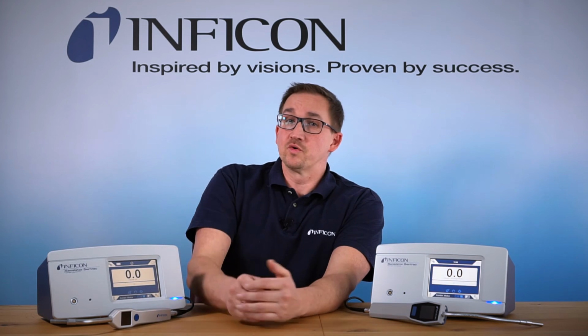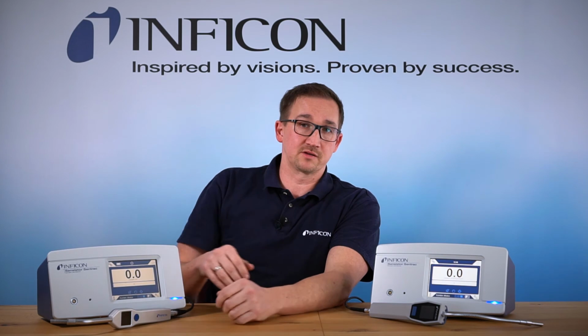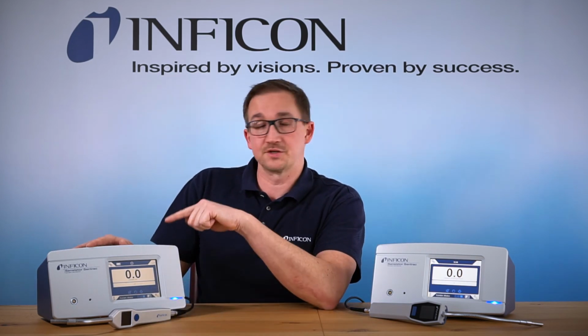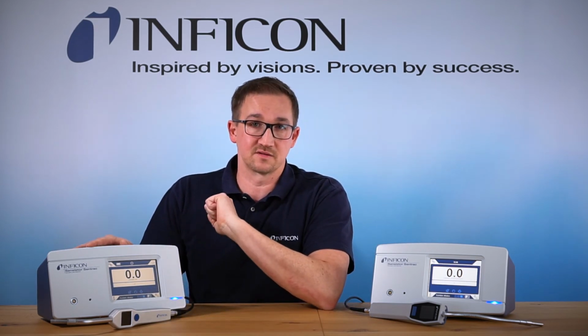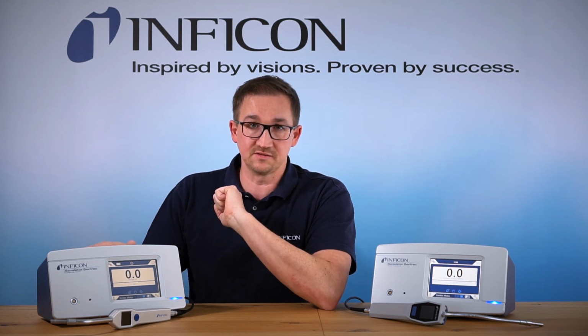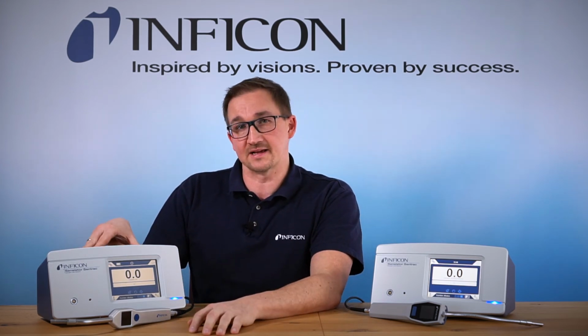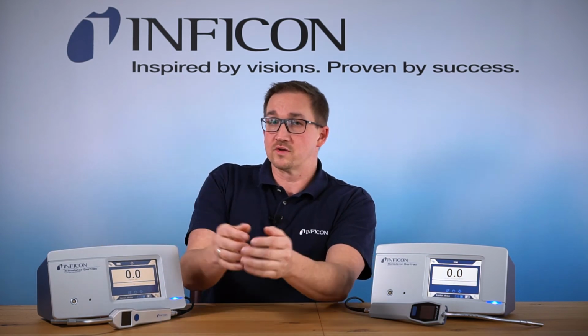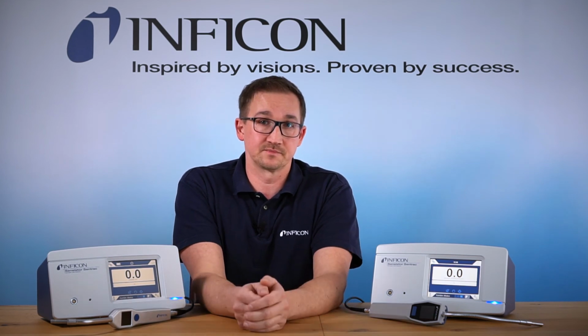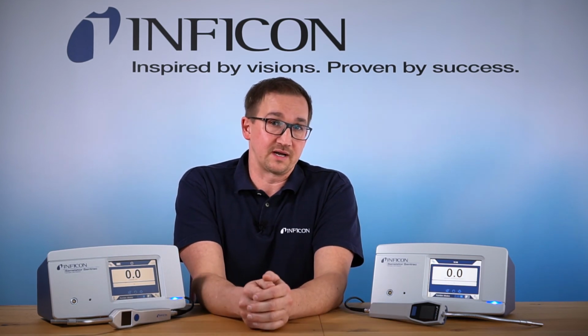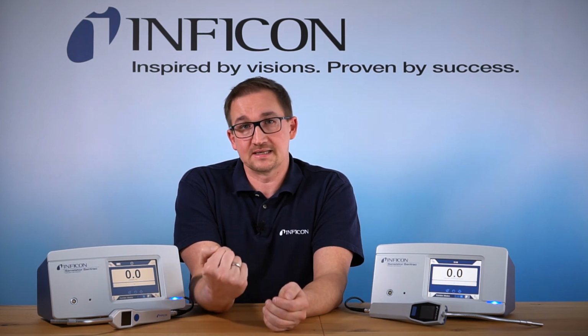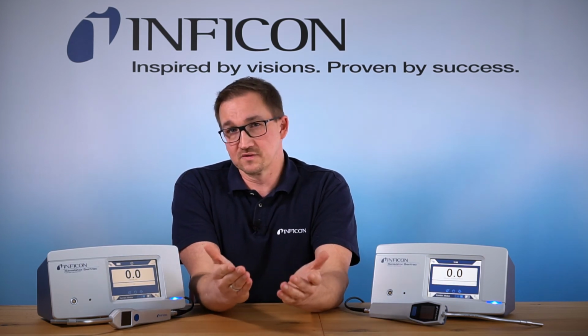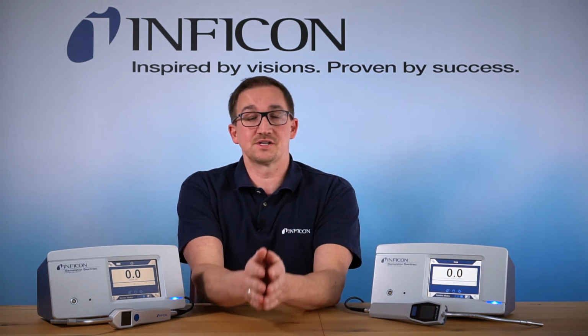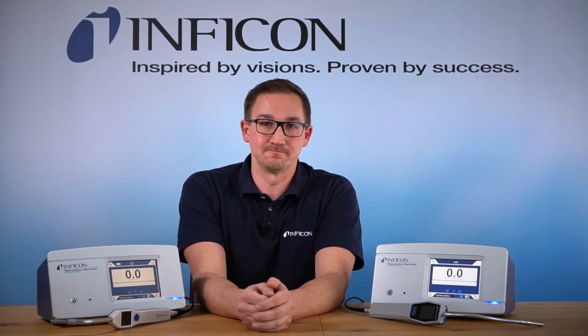Bigger leaks in the range of fluid tightness, 10⁻³ millibar liter per second or even bigger, can easily be located with the standard version of Sensistor Sentrac. This version is optimized for best selectivity, and high selectivity simply means fewer cross-sensitivity issues. So you see, for many different applications we have different leak detector options available. And in case you are not sure yet which of these units is the best choice for your application and your individual needs, simply get in touch with us. Sprechen Sie uns einfach an.